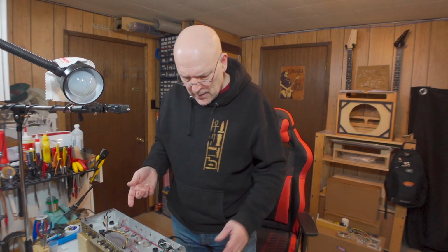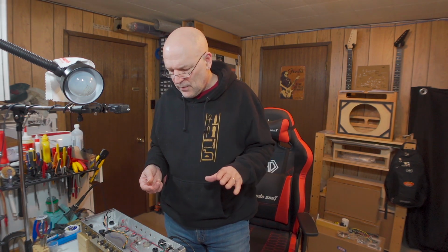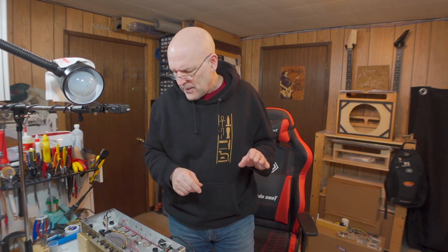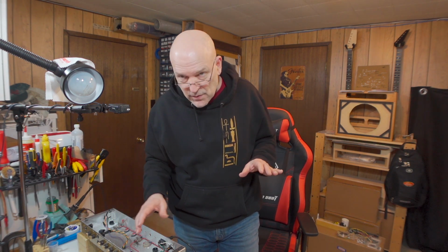So that said, we're ready to test. I am going to plug it in right now. First thing we're going to watch for, the indicator lamp should still light, and this bulb should not do anything. If that's good, we're probably okay. Before I turn the current limiter off, I'll get my head close to see if I can hear anything, maybe arcing or sparking, or notice any odd smells.